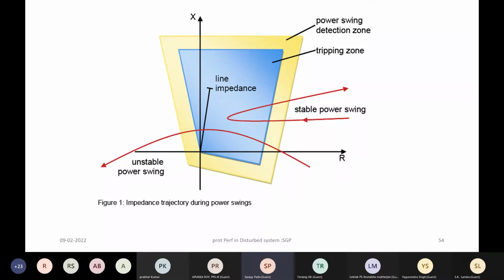So that is the advantage of this characteristic. The advantage from the fault perspective is also that high resistance faults, which are often experienced, can be better sensed by this characteristic because you have a better resistive reach. Unlike in the circular characteristic, where the resistive reach is decided by the diameter of the circle, which is basically the reactance of the line. So reactance decides the resistive reach. So there is a limitation on high impedance or high resistance fault detection. So the polygonal characteristic is preferred.